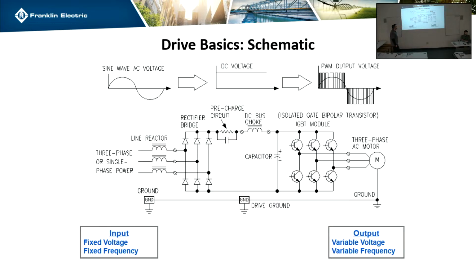So this is the input circuit generally. This is from our P drive, but this is kind of just an across the board how VFDs convert your voltage. You have three-phase AC power coming in, goes through your line reactor, goes through a rectifier bridge, which turns it from AC voltage to DC. The drive stores it using the pre-charge circuit and your capacitors. Some of the drives have a built-in DC choke. It just depends on the size. And then the drive just chops it up and sends it out as a fake AC wave to your motor that it can control. And that's how you get your basic control.